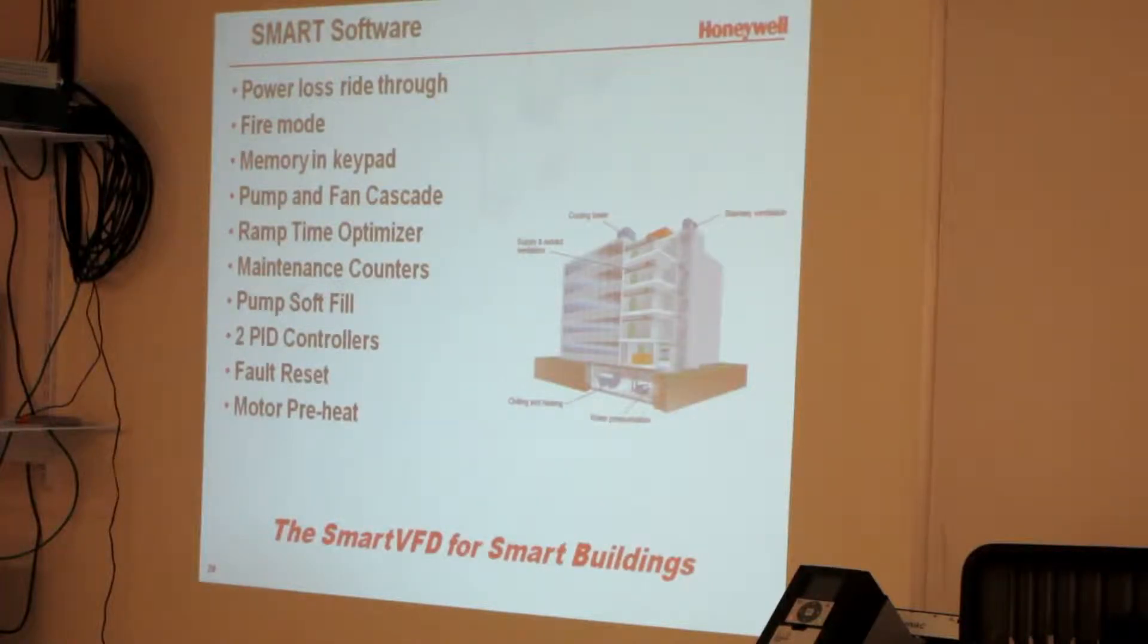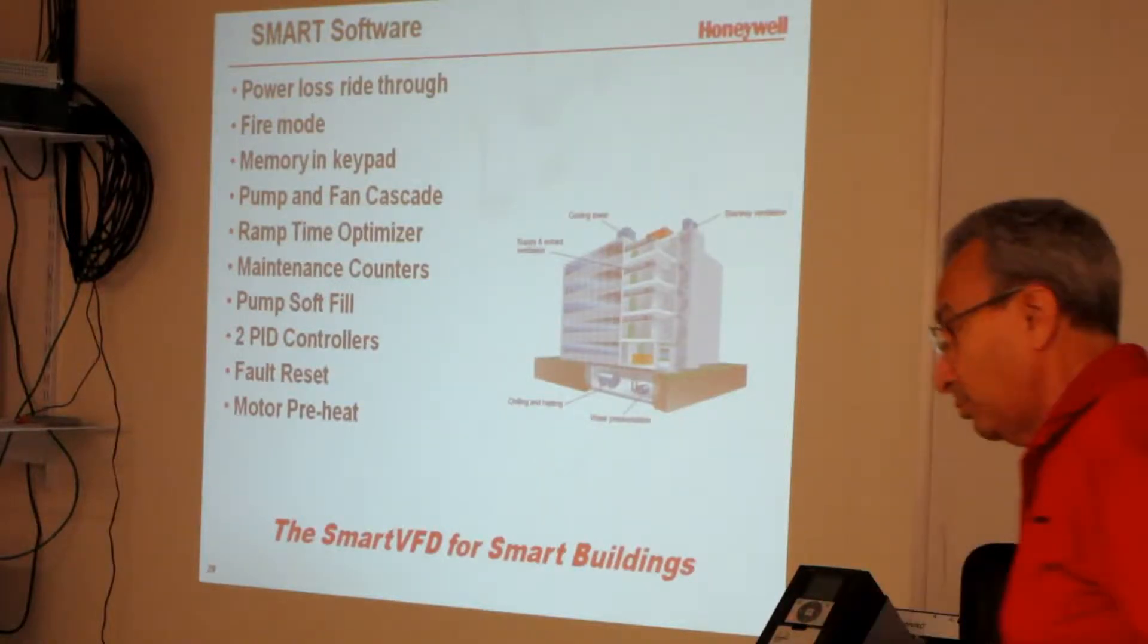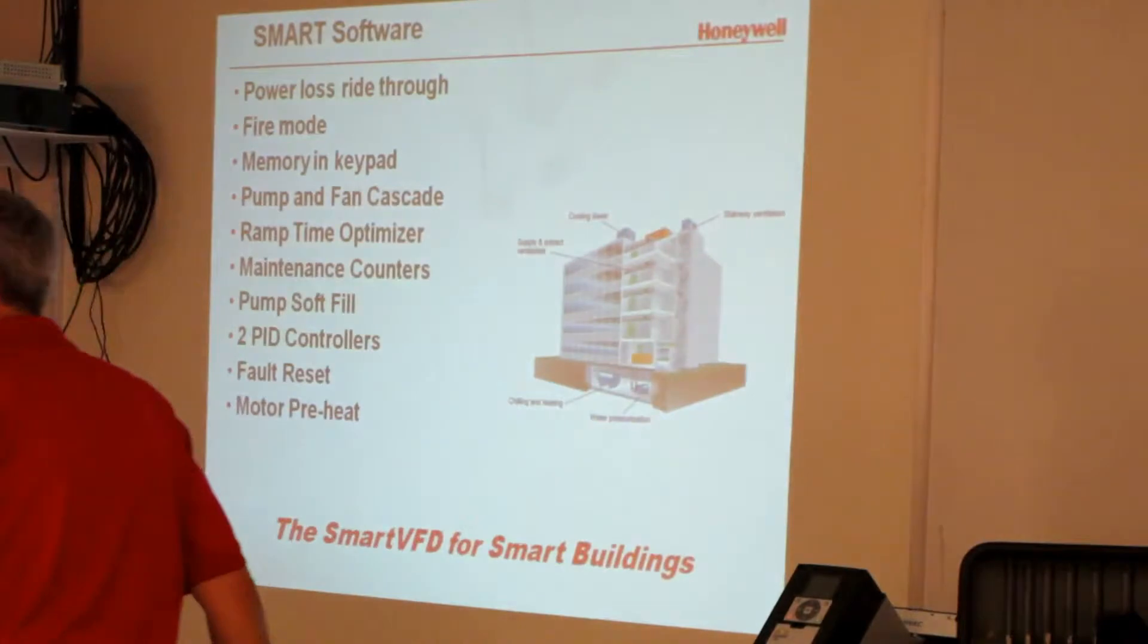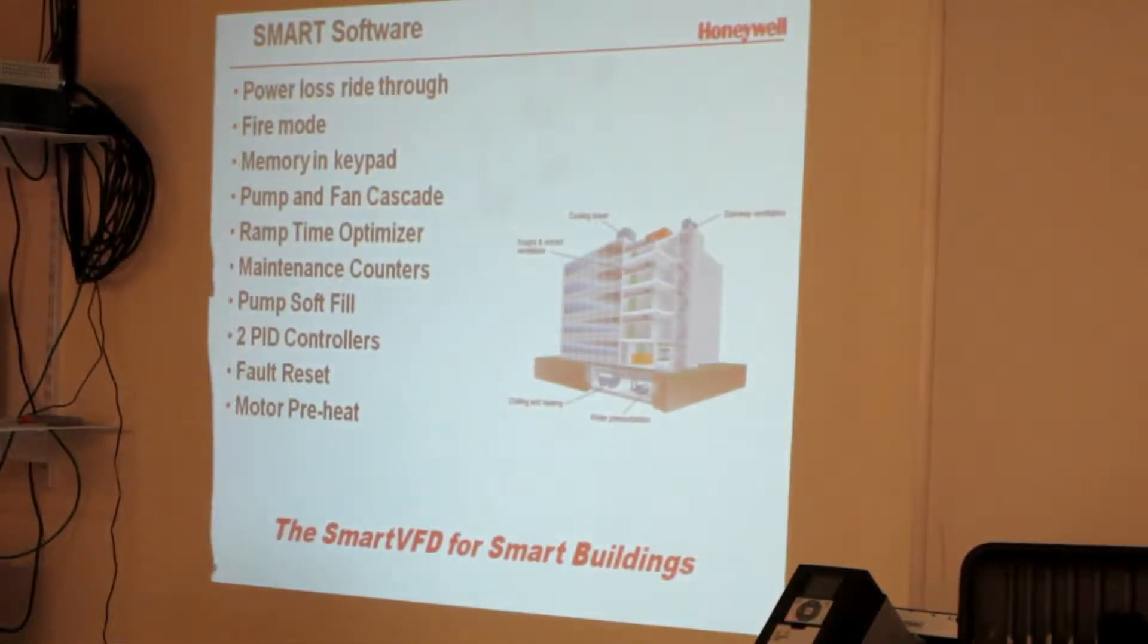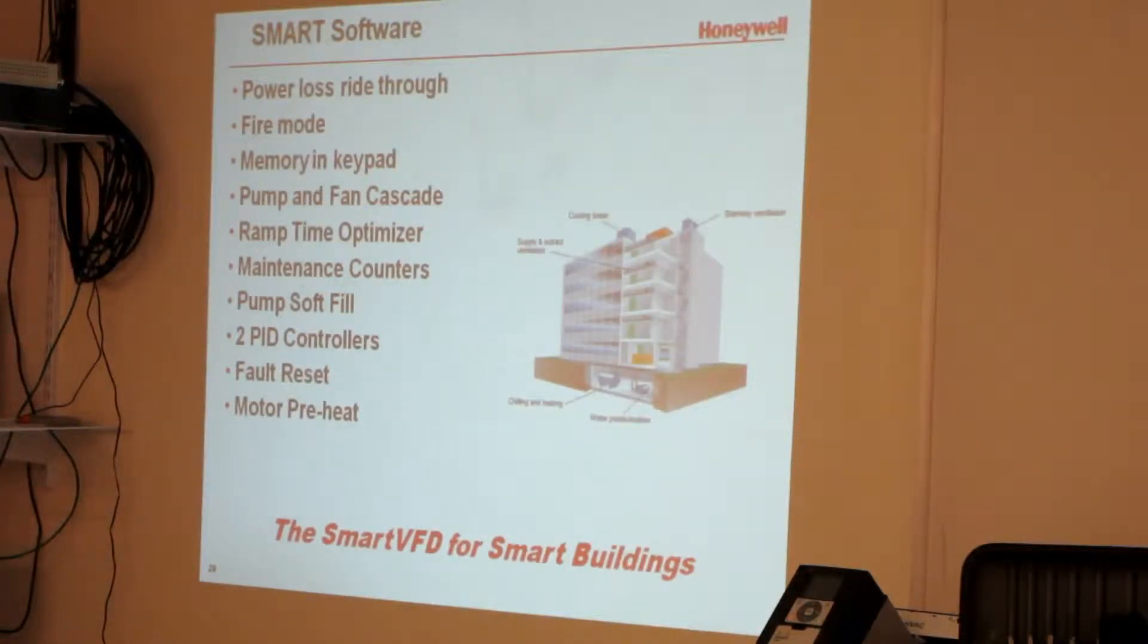It's not uncommon to see these drives or any drive inside the air handler in the panel, because normally the panel is not that cold or hot. It's grabbing some of that conditioned air. So humidity isn't a problem? No, those coated boards help that. Of course, hosing it down with a deep cool is probably not a good idea. You have the ability to hook up two PID controllers to it and switch between them.